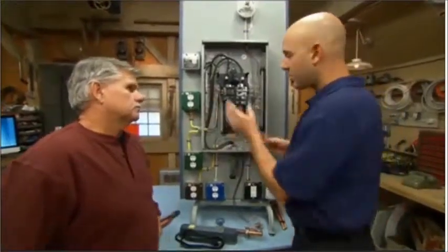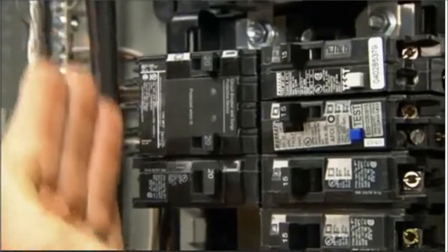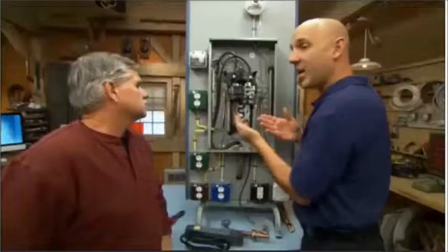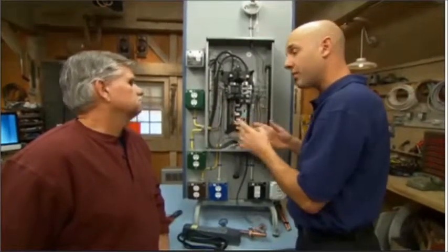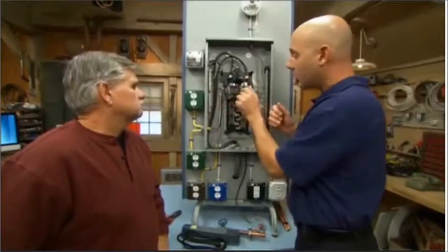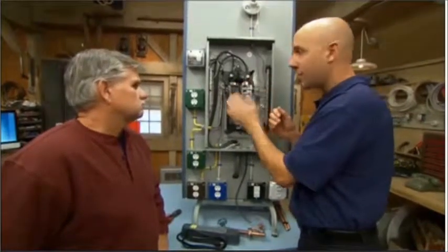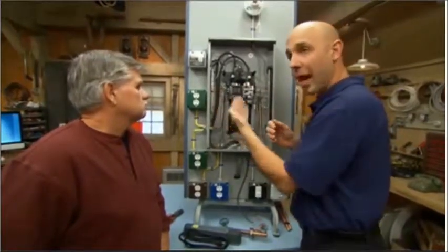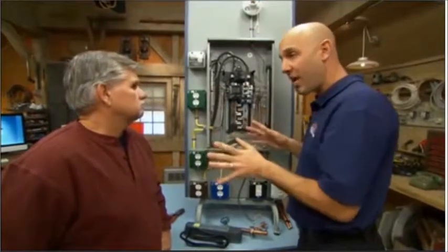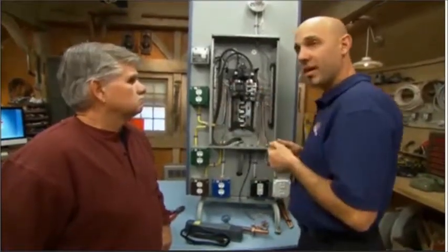So we have this surge protective device combination circuit breaker, and it replaces two circuit breakers. In this case they were 20s. We take the device, put it in its spot, put the branch circuit wires back on the circuit breaker like nothing ever happened, and now it's a whole house protective device right there at the panel.